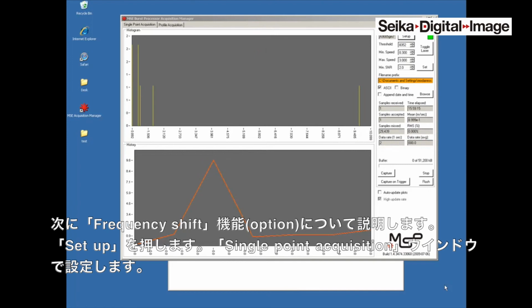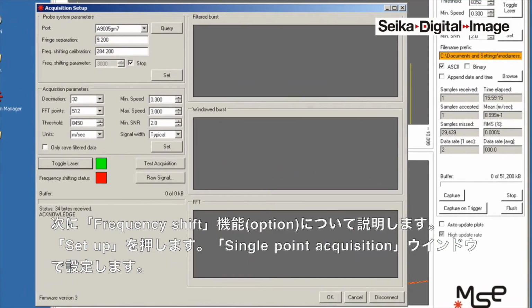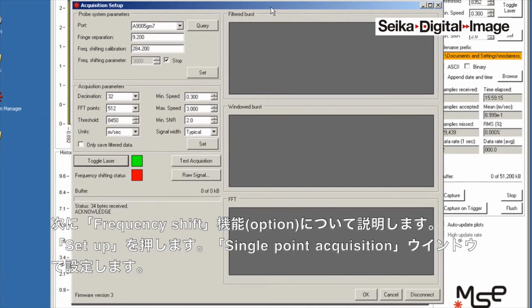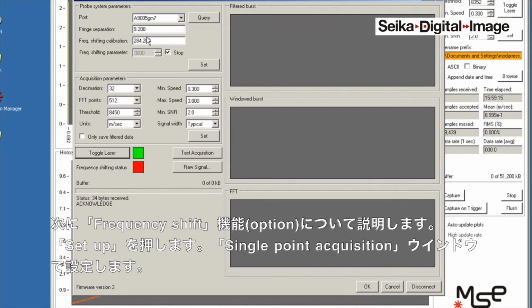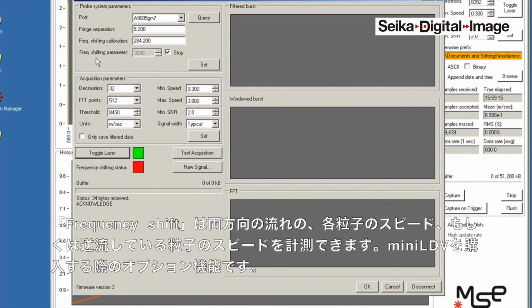For those probes that have the frequency shifting option, I would like to talk about how to set it up. You go from the single point acquisition, you push setup, and the screen shows here as it was before, somewhat. The frequency shifting parameter. The function of the frequency shifting is to allow you to measure both the direction and the magnitude of the speed of the individual droplets or particles, or to be able to make measurements in highly turbulent flows. In both cases, you do need frequency shifting, but it's an option that you can provide, but it has to be done at the time of the ordering.